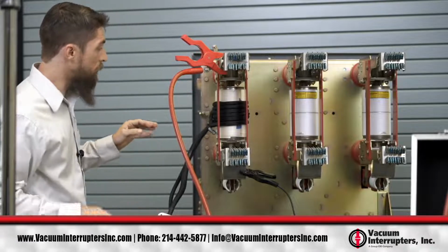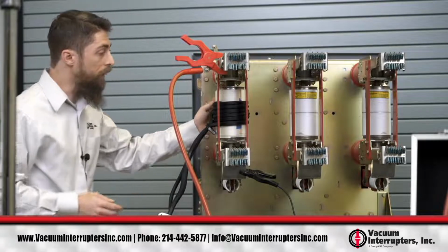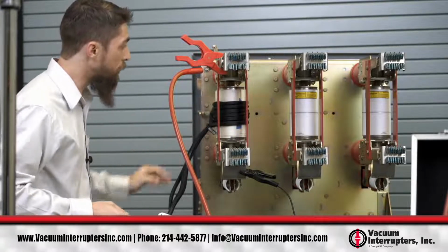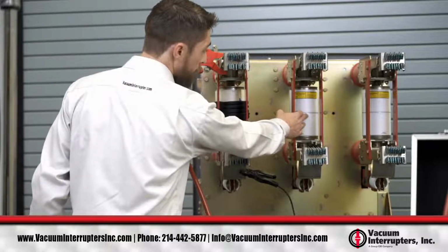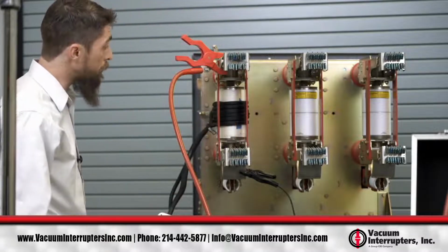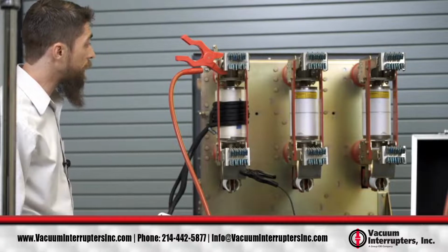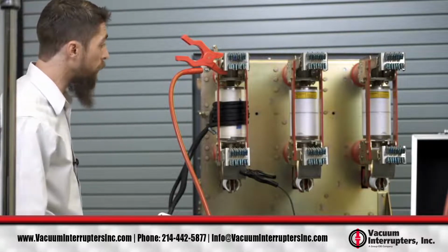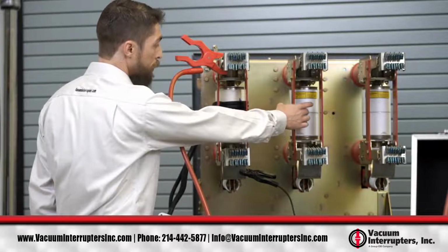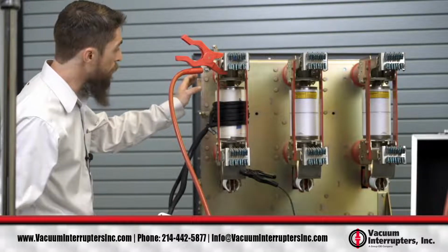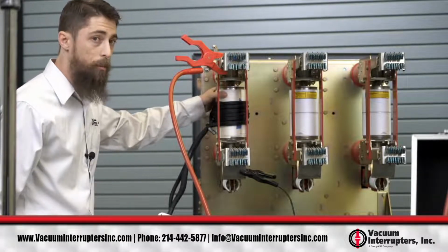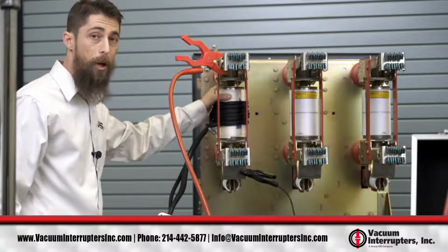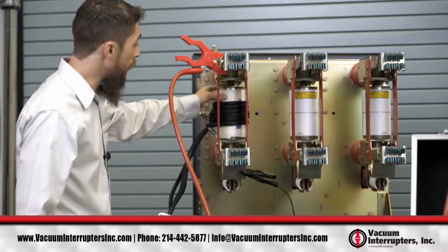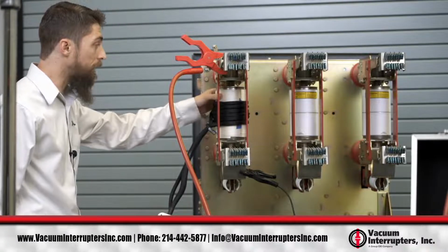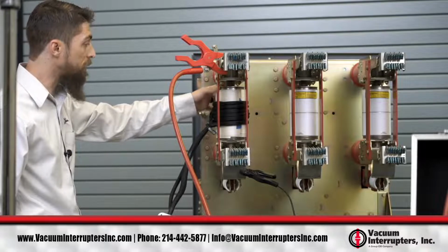You also want to insulate it from any type of high voltage. On these vacuum interrupters, there is a center shield band, which, if it's unable to insulate the voltage, then there will be high voltage on this center shield band. So we've wrapped transformer winding paper, Nomex, or some people call fish paper, around the vacuum interrupter first, in case the high voltage can't be insulated by the VI.